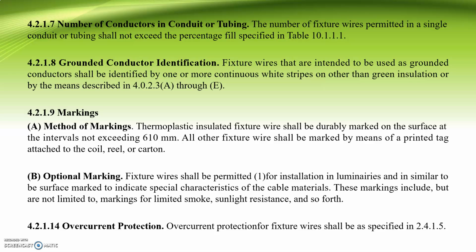So chapter 4.2.1.7, number of conductors in conduit or tubing. The number of fixture wires permitted in a single conduit or tubing shall not exceed the percentage fill specified in table 10.1.1.1. So chapter 4.2.1.8, grounded conductor identification. So fixture wires that are intended to be used as grounded conductors shall be identified by one or more continuous white stripes on other than green insulation or by means described in 4.0.2.3 A through E.